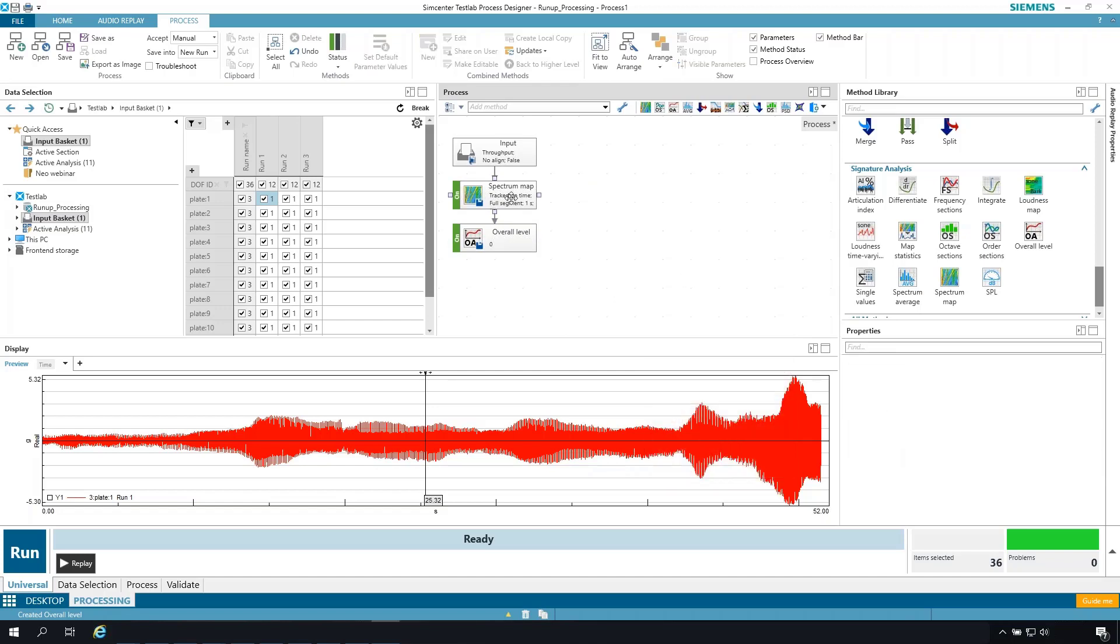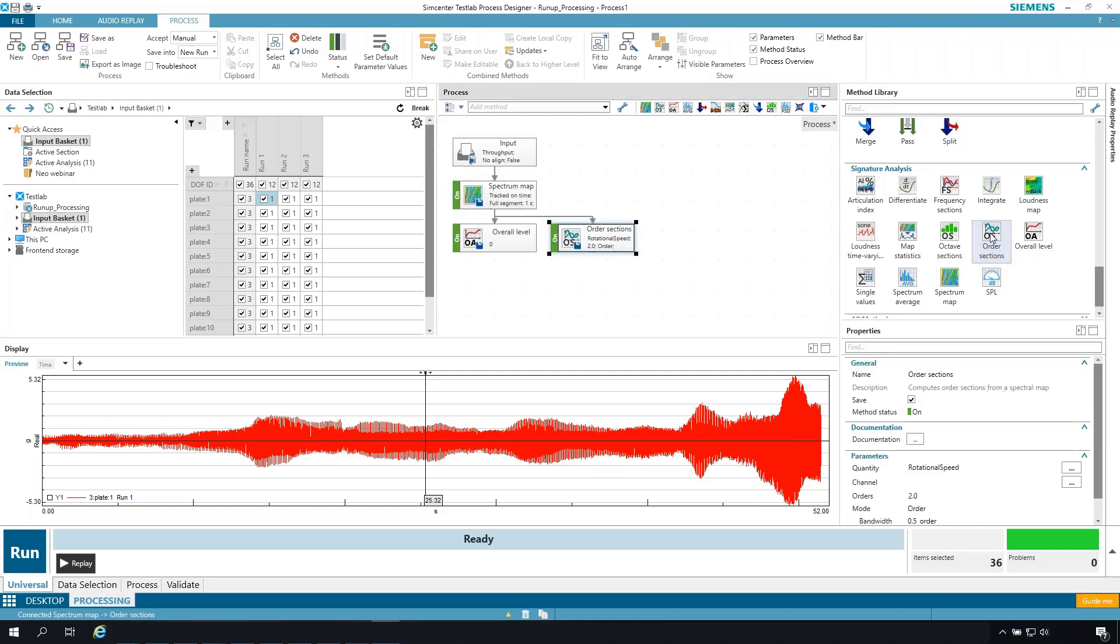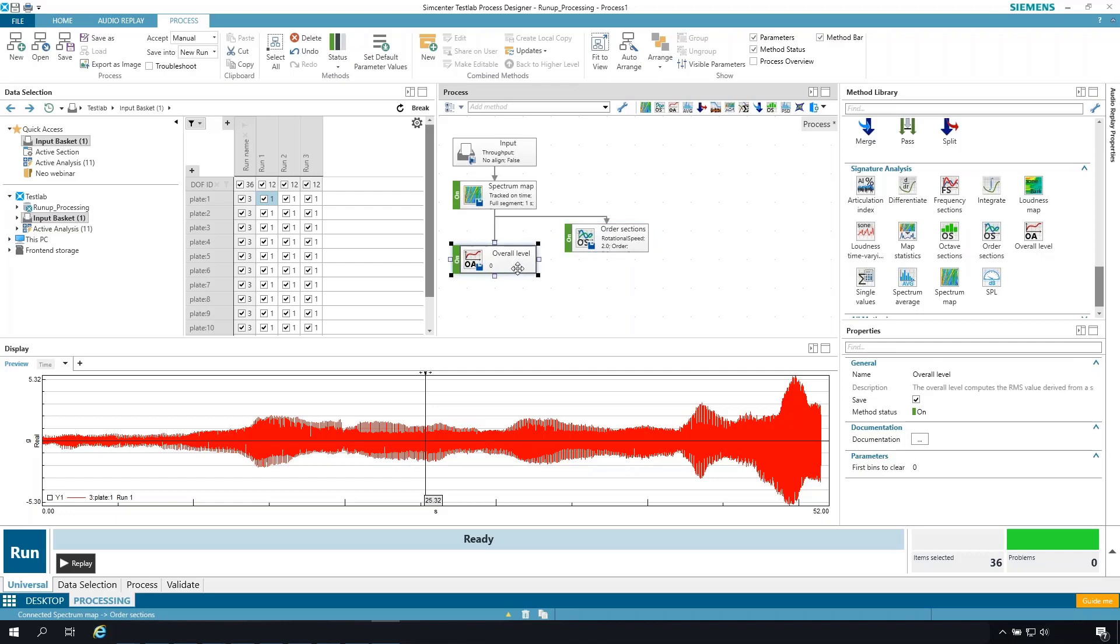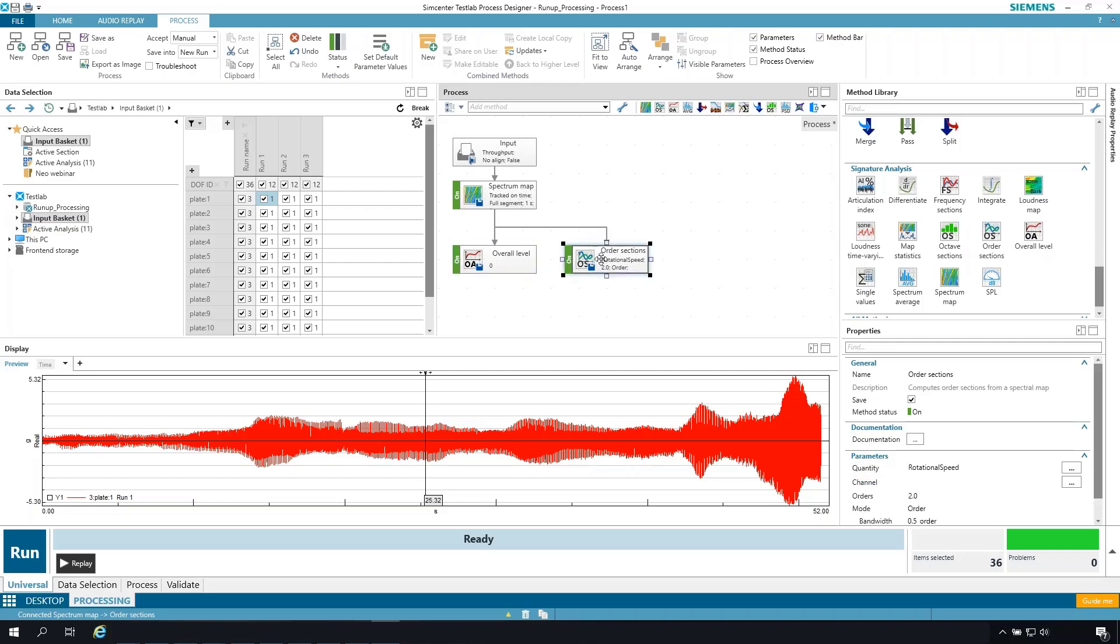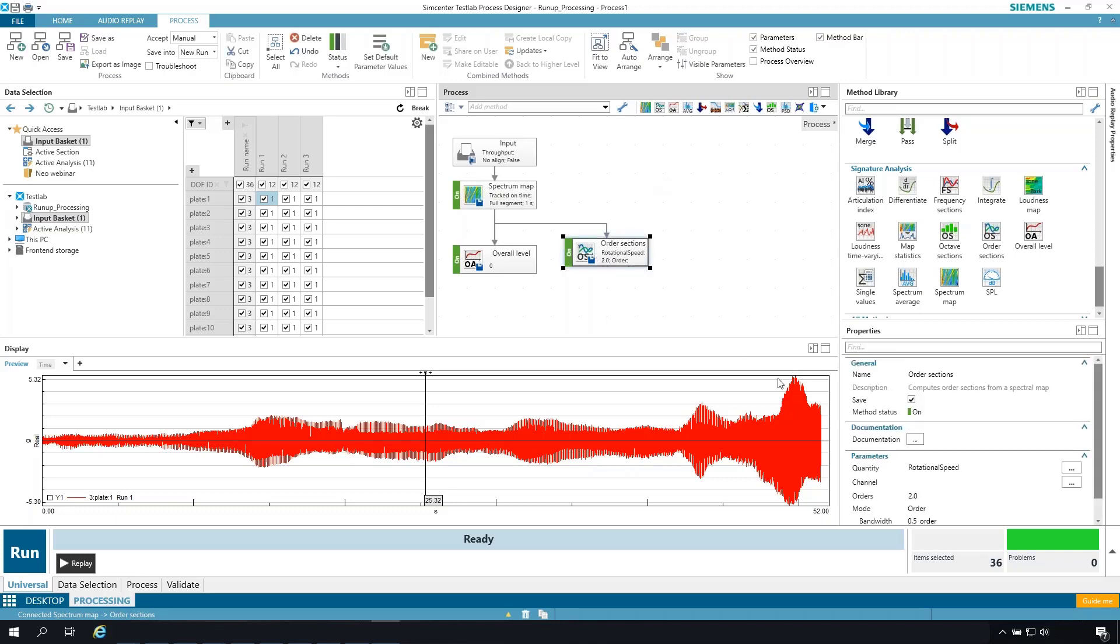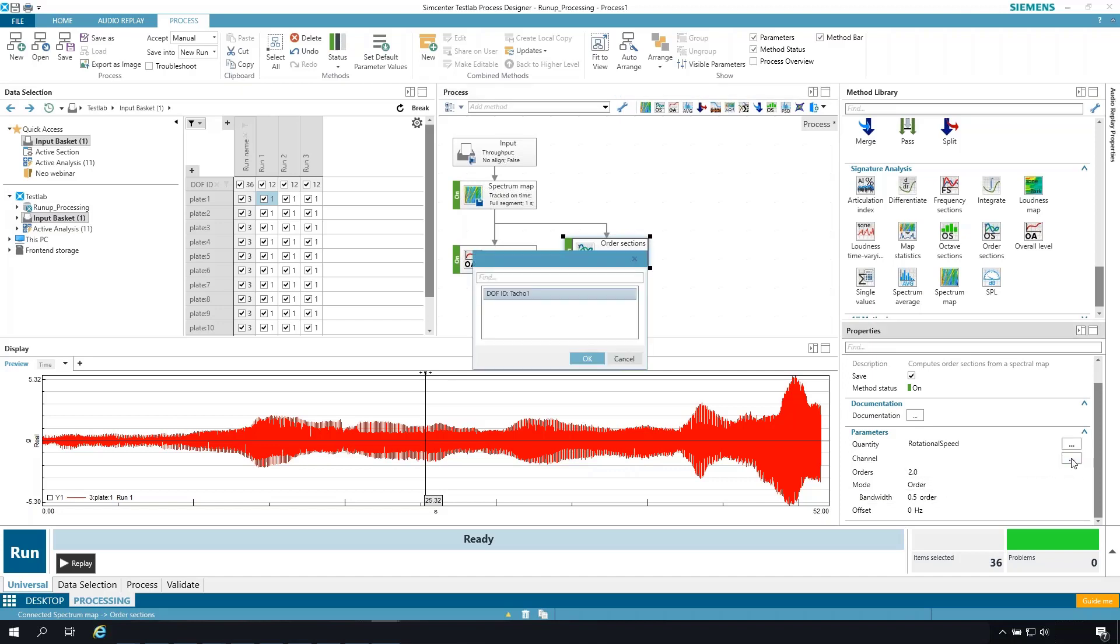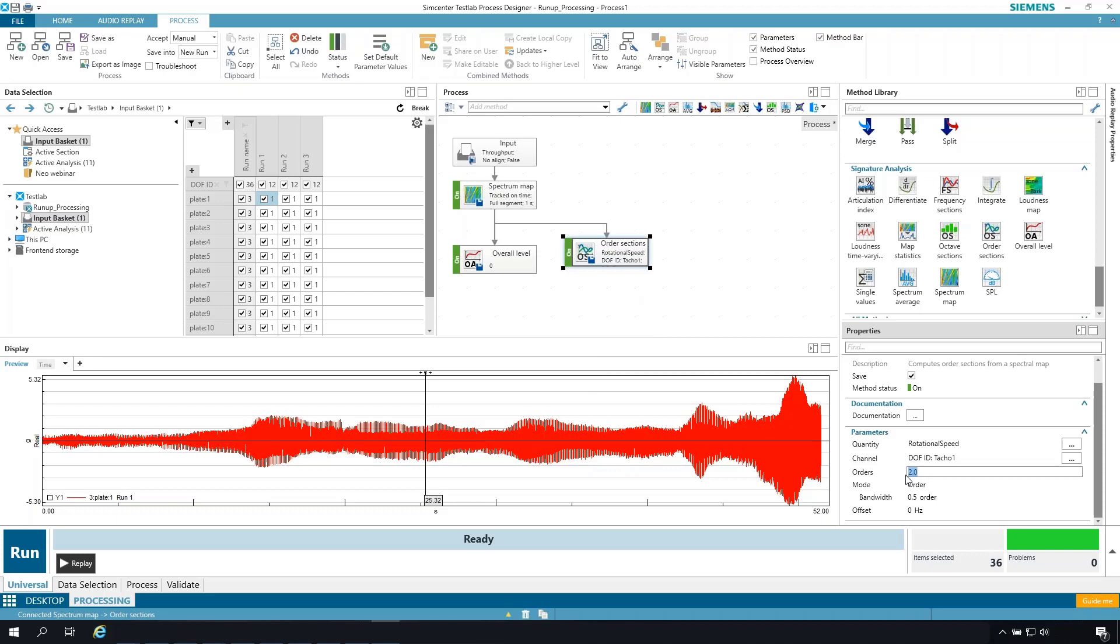Also from a spectral map, I can perform some order section calculations. So we're going to let it connect order sections. Let me move these a little bit so we get a clearer view of the arrows. We're going to transfer the spectral map data both into overall level and order sections. Now, if I select the order sections, you can see down under the properties, the properties for the order sections method. One of those major properties is the channel to calculate the orders from. That needs to be identified as my Tacho channel, Tacho01. And then which orders I want to process. It's defaulted to order 2.0. I don't know that that's really what I want. So at the moment, I'm going to take this process and turn it off. I don't want it to calculate orders yet until I have a look at the spectral map.